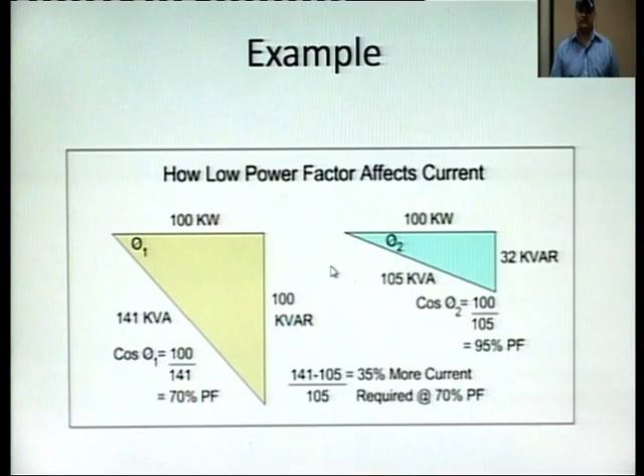For larger kVAR, we require larger current or larger kVA. Similarly, if we have 100 kilowatts of real power and 141 kVA of apparent power, then we must use larger transformers. There is a lot of difference between the kVA ratings of 105 and 141. So we require larger transformers and larger generators if the kVAR rating is higher. So this is the example of how low power factor affects the current.